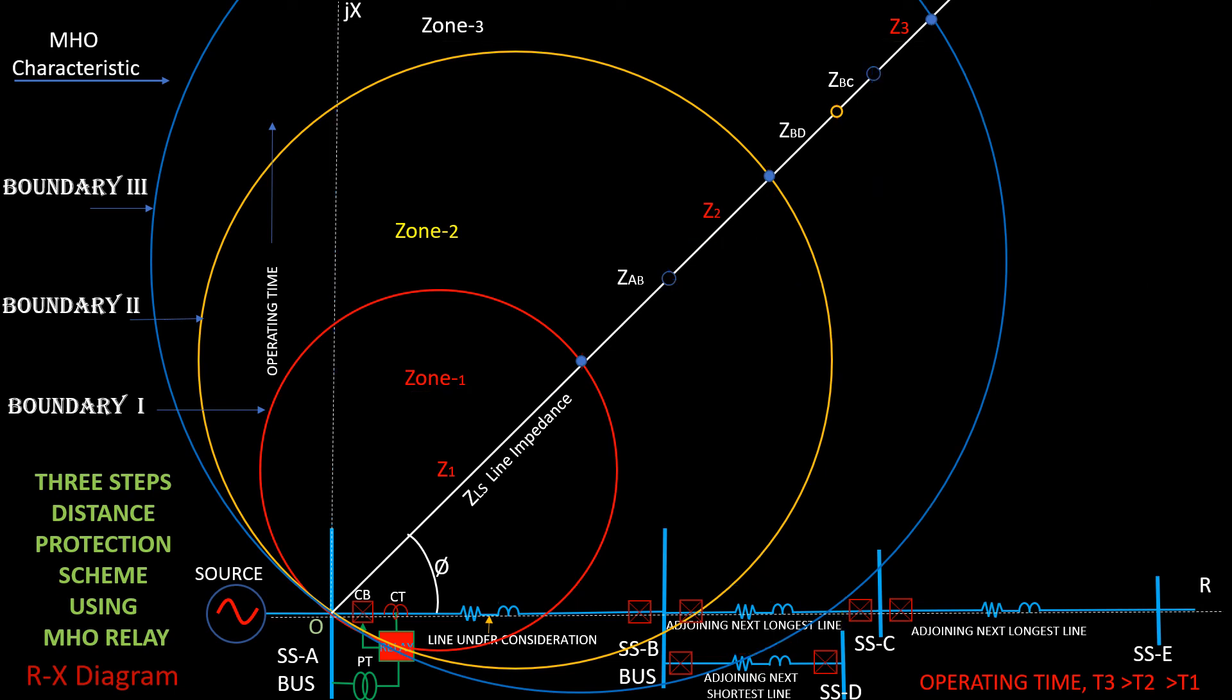This was the MHO characteristic of 3 step distance protection relay. Relay will calculate fault current and fault voltage to obtain impedance during fault.